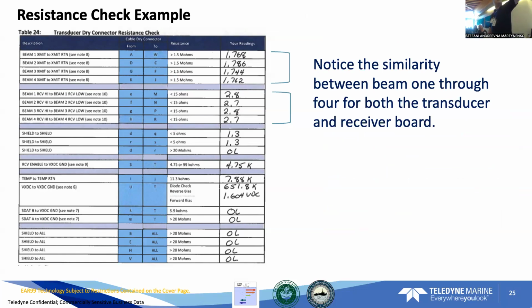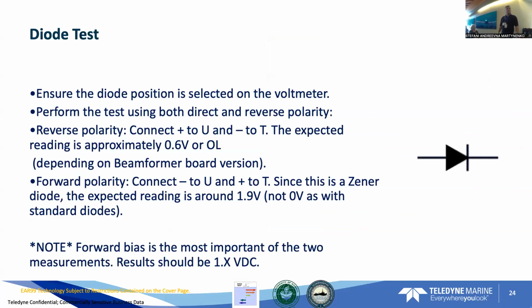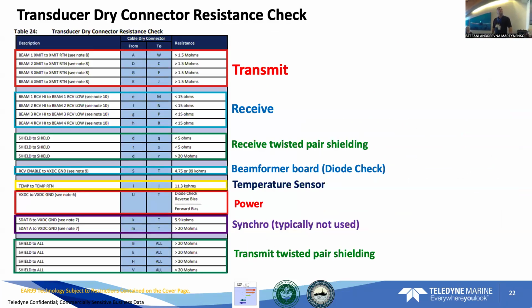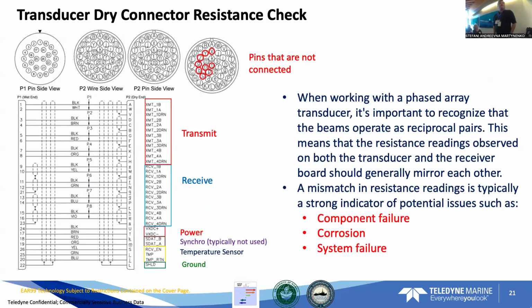This is one I just recently took in Singapore. So you can tell everything is kind of the same, which is important because it kind of mirrors each other and duplicates everything. So mismatched readings will typically be a strong indicator that you either have some sort of component failure, or your beamformer board could be damaged, or there could be corrosion in the system, or just some overall system failure.